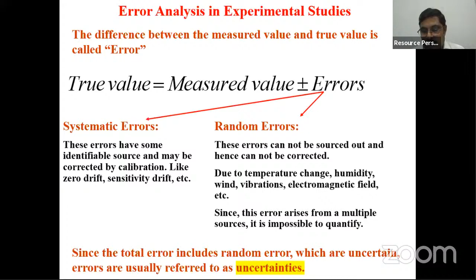Basically, the true value, the actual value, will be equal to the measured value plus the error. This error can be a systematic error. The systematic error is due to improper calibration or the inherent features of the instruments, which can be determined by using a calibration. Whereas the random error is mainly random, which means you cannot predict the source. It can be anything, maybe due to improper usage, environmental influence, or the influence of electromagnetic effects, etc. These sources cannot be traced. Since this error is random and uncertain in nature, the error is called uncertainty. Okay. So now we will see how we can estimate the uncertainty.